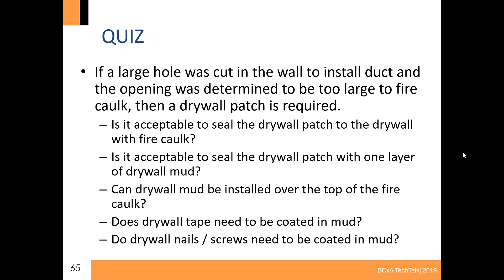So, is it acceptable to seal the drywall patch with fire caulk? No, drywall to drywall seams must be coated in mud. There is no UL listed system to use fire caulk between drywall and drywall.